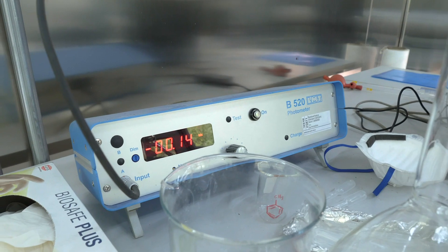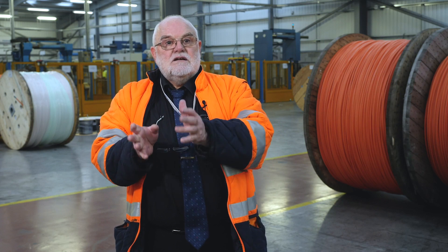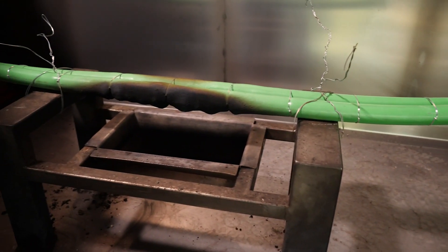You test for smoke in a 3m cube — how much smoke is generated. You test what's in the smoke. You then burn a sample or decompose a sample of the material and analyse the gases coming off.